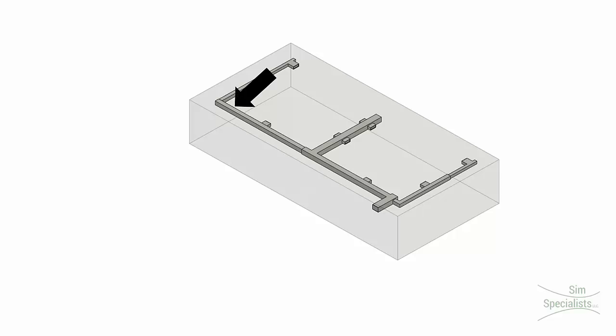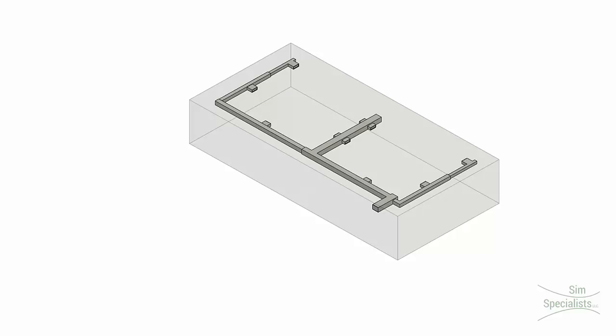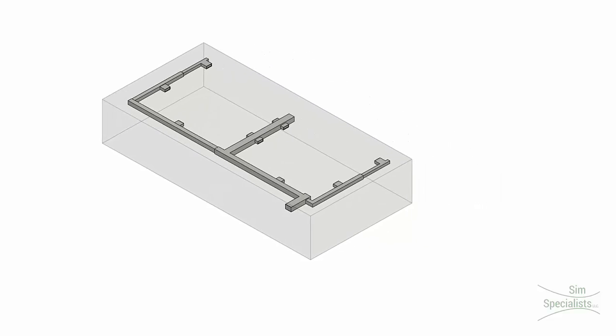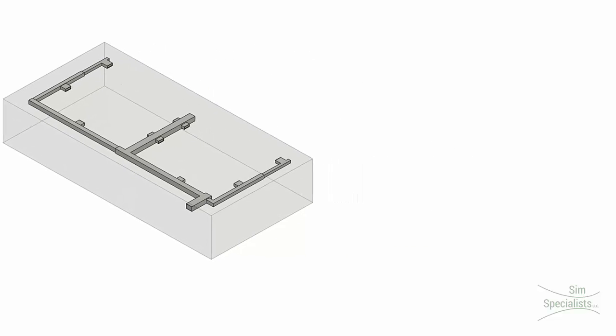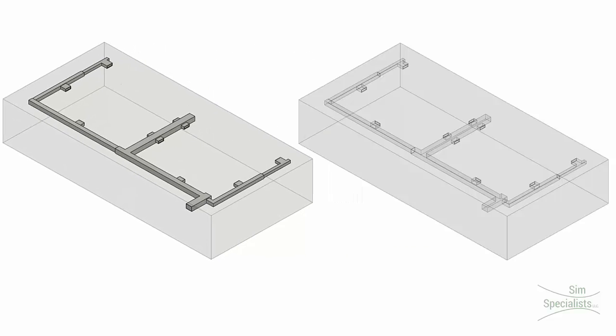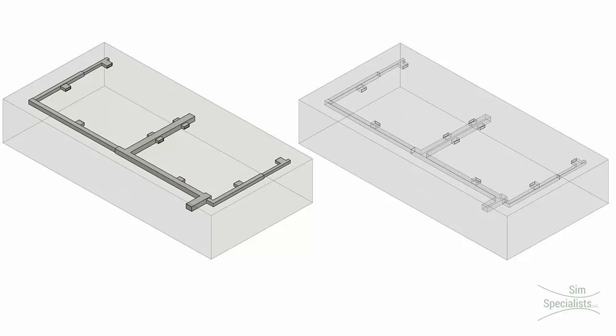Simulating the complete ducting layout will increase mesh count due to the long narrow passages and thin duct walls. When focus is on overall room performance and supply flow rates are known, the ducting can be suppressed to become an empty void in the model. Supply flow is represented with boundary conditions to decrease overall complexity.